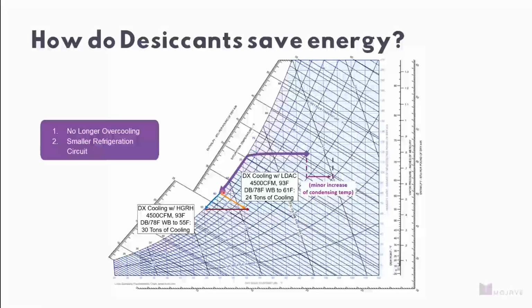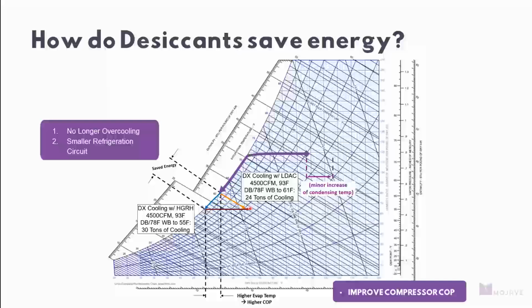So we're eliminating all of that, stopping short of our final target condition with the DX system, and then leveraging liquid desiccant to do the harder effect. I say effect because it's not work, because there's a conservation of energy happening. What this looks like psychrometrically is, as the saturated air off that cooling coil passes through the liquid desiccant media, you're converting latent energy to sensible energy in equal parts. So conservation of energy happening. What that looks like is you ride an enthalpy line down to the same target condition without crossing any enthalpy lines, and you save a pretty tangible amount of energy by eliminating the work involved to get to that same target dew point. And again, you're reheating that air because you're going from a vapor state to a liquid state, and that heat has to go somewhere. So it stays in the air and passively reheats you up to a target condition.